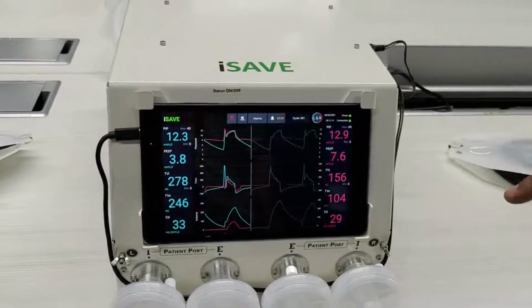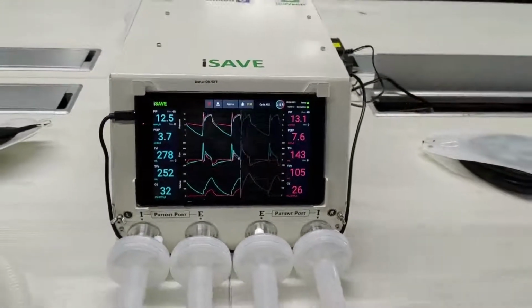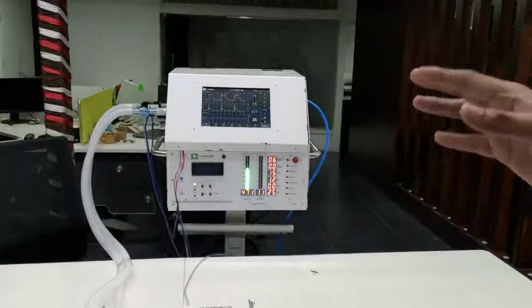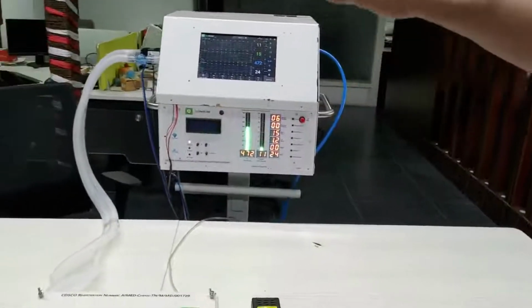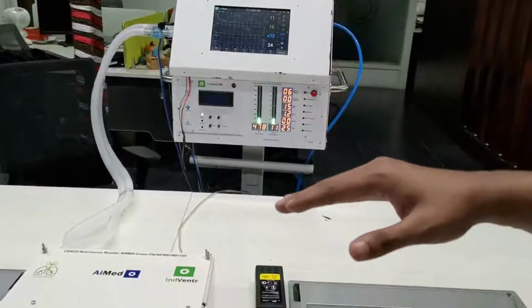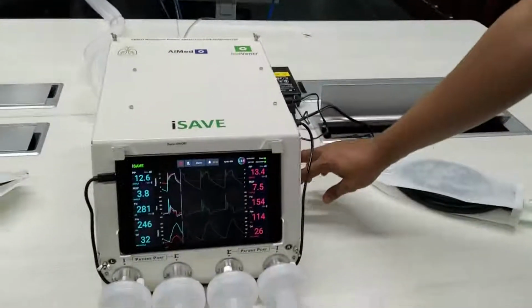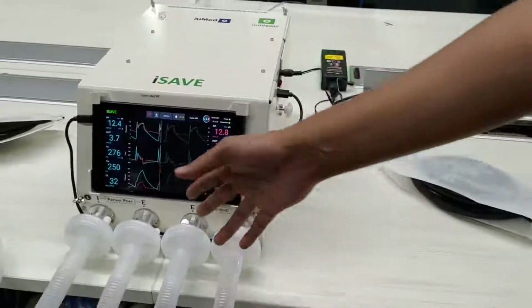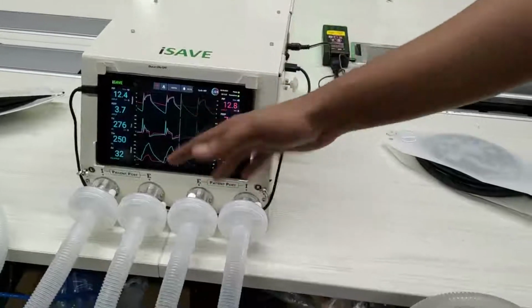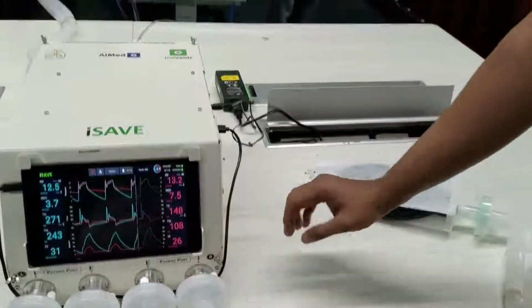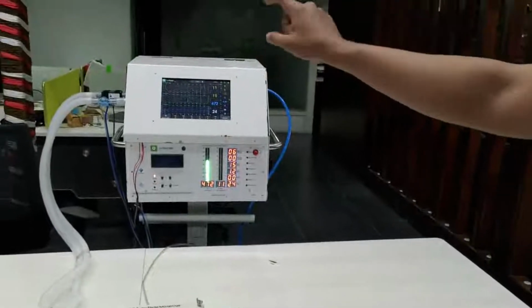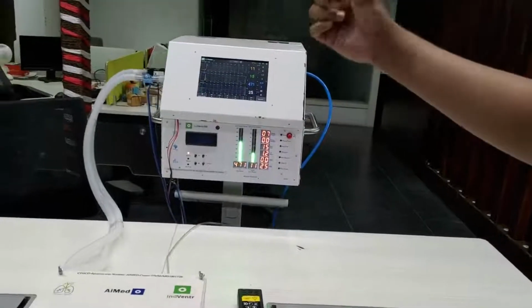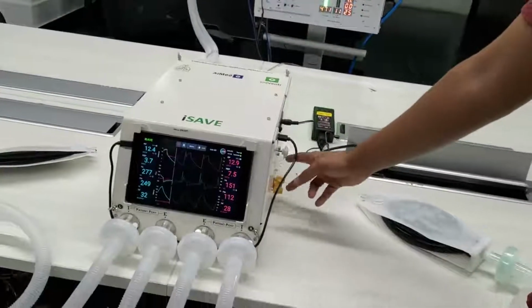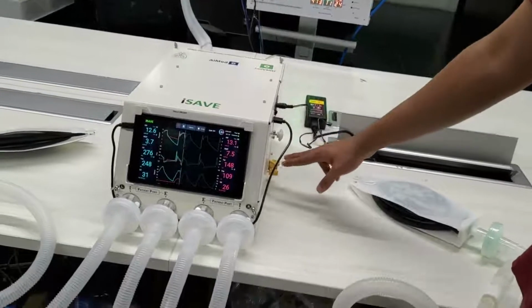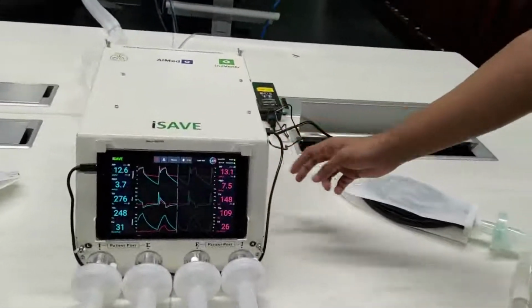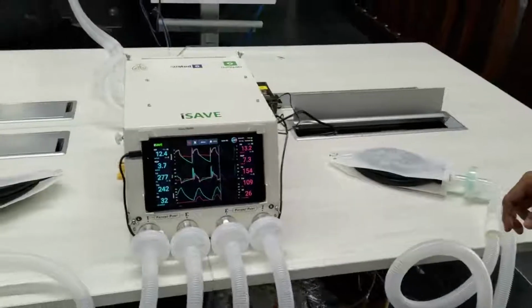In volume control mode, this is not what we do. We first reduce the ventilator volume on the ventilator to half of what it was. Then we close this valve, and then we take it out and replace the patient in. And then we increase the volume back to what it was originally. And then we open up the valve. Okay, thank you for watching this demo.